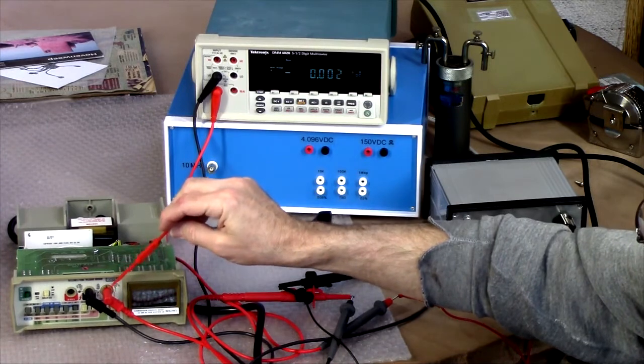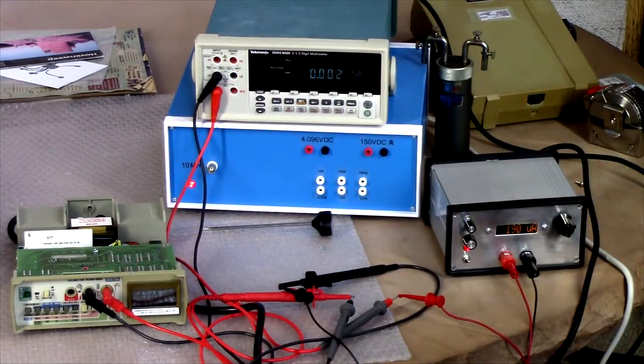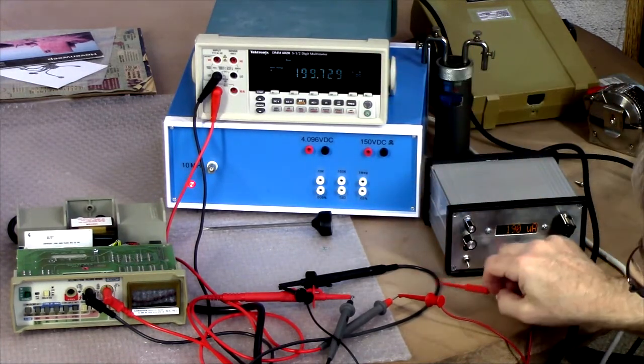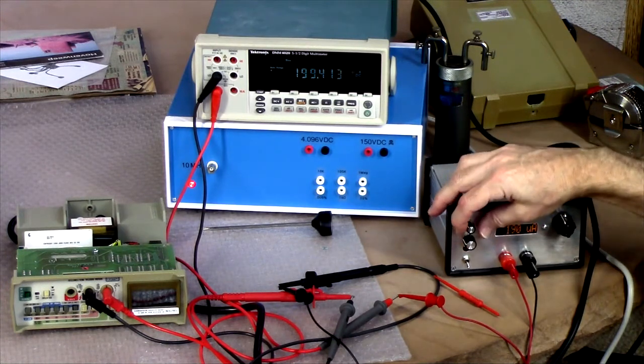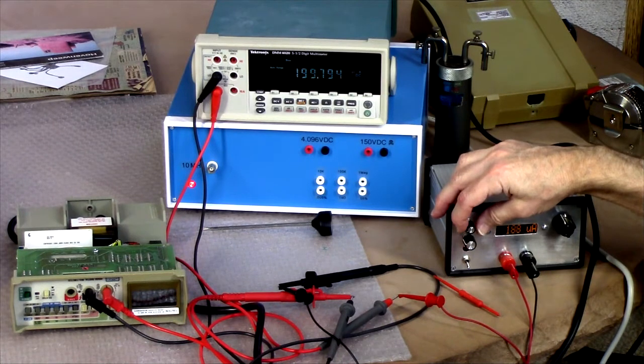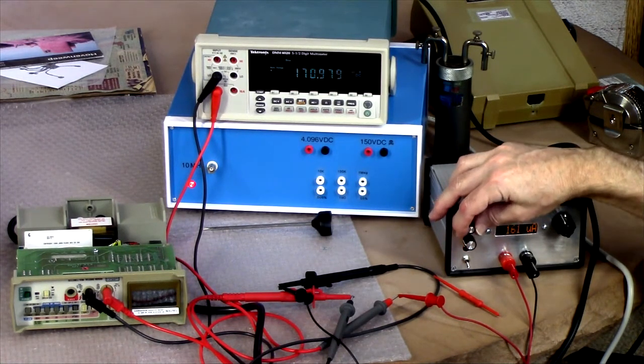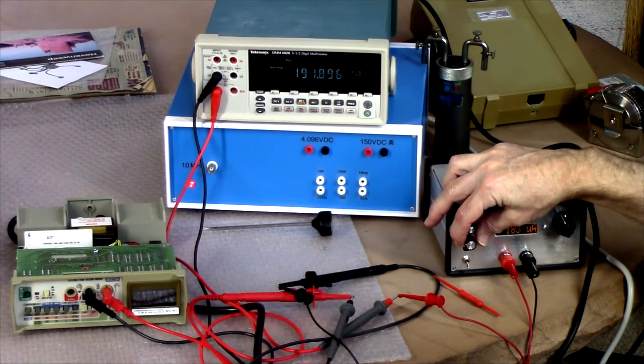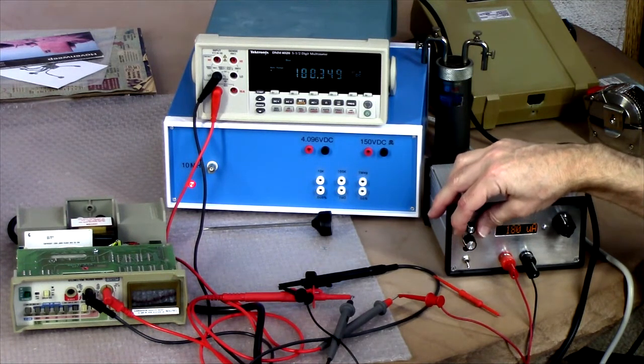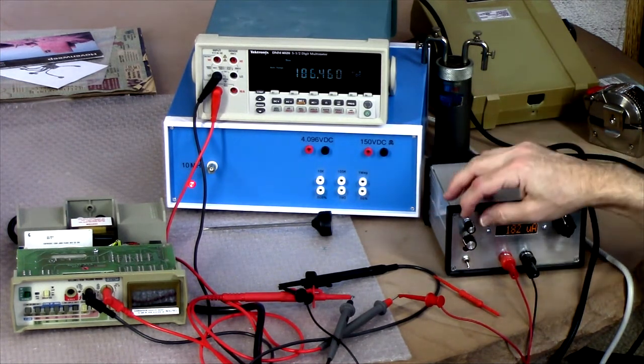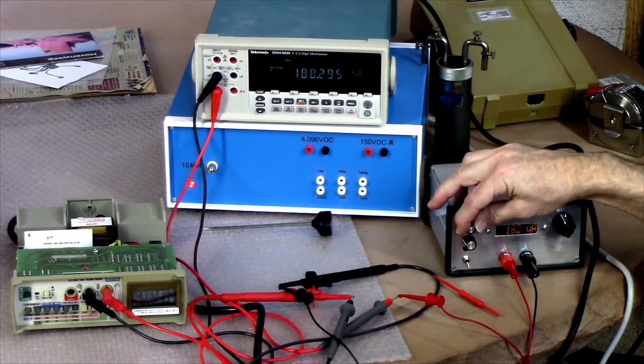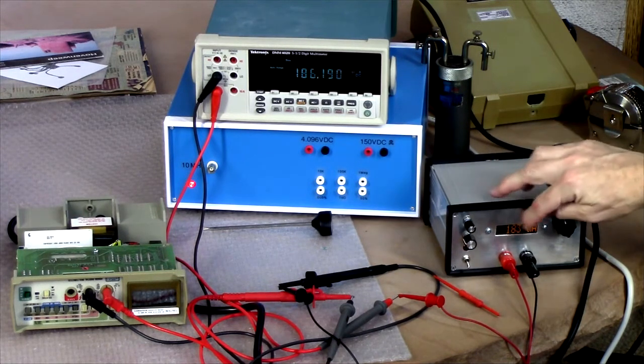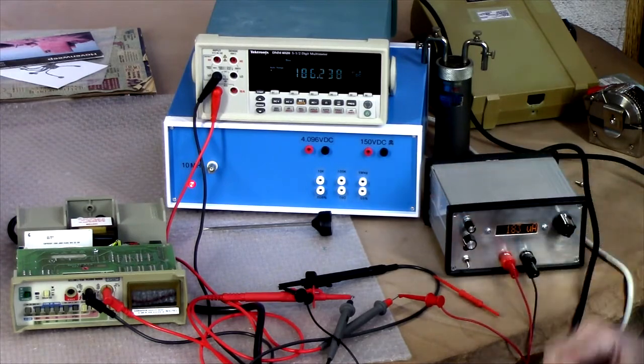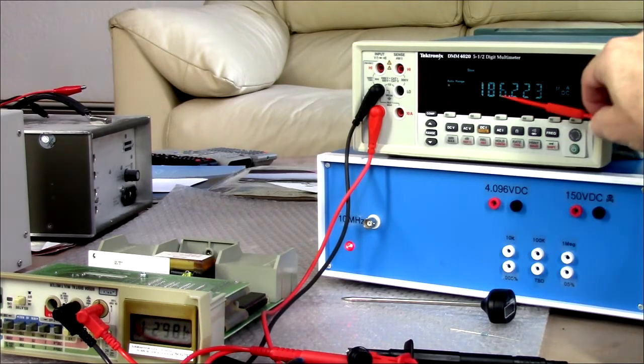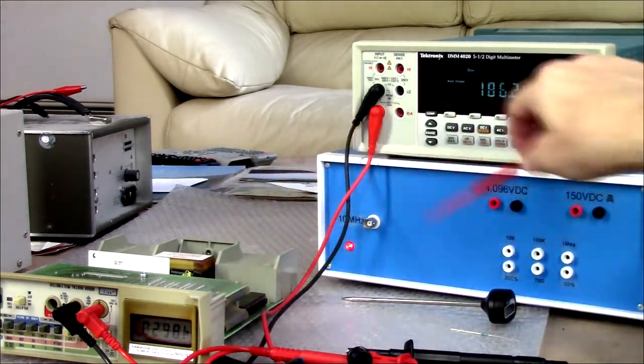Set it to 200 microamp scale where we've swapped the leads over to where we're measuring current. And now if I flip that on, okay, 199. Well, I can do better than that. Whoa, that's way off compared to the reading. We seem to have a slight disagreement between the readout on the instrument. This is like that power supply. Of course, I built this myself, so I don't trust it. Anyway, these should match. 186.2 something, 186.2. Yeah, okay. Call that good.